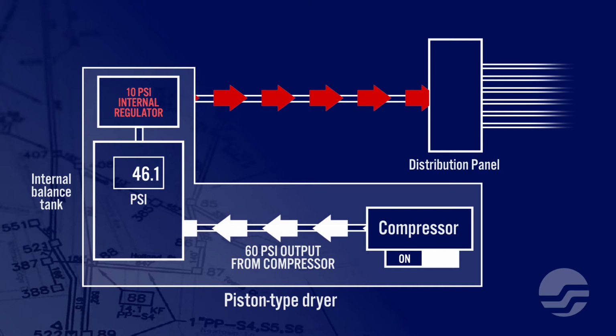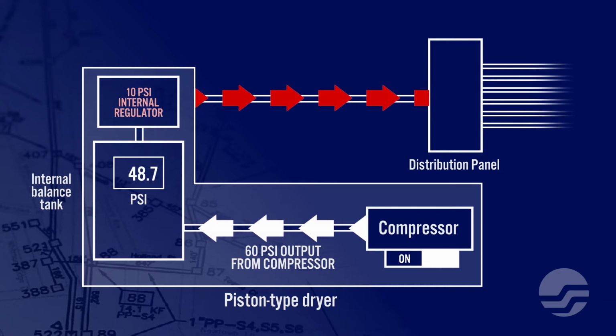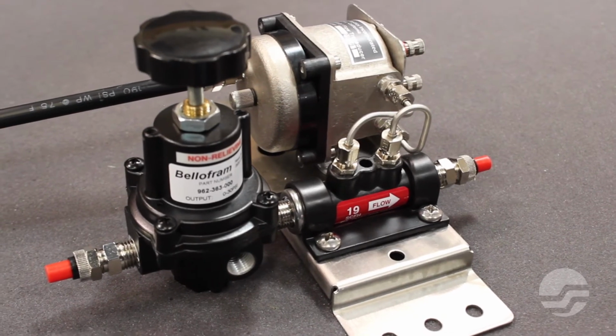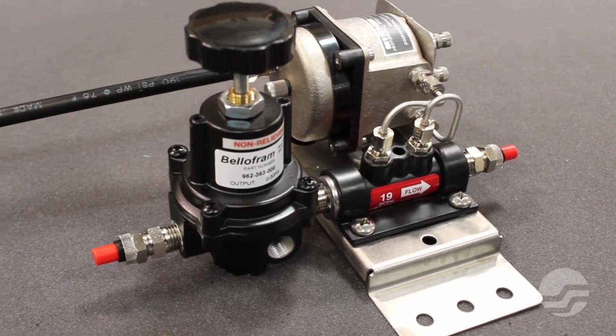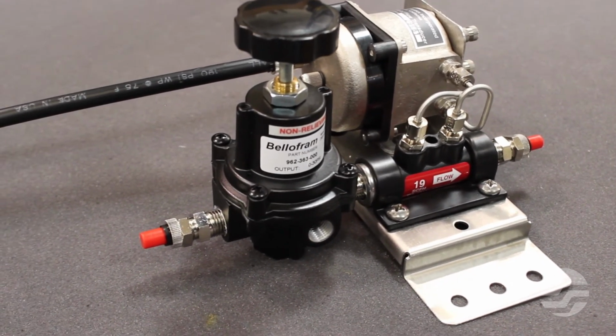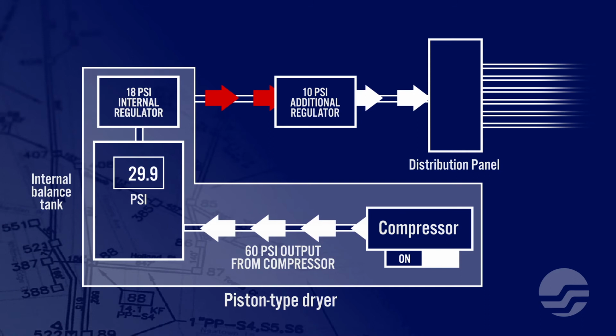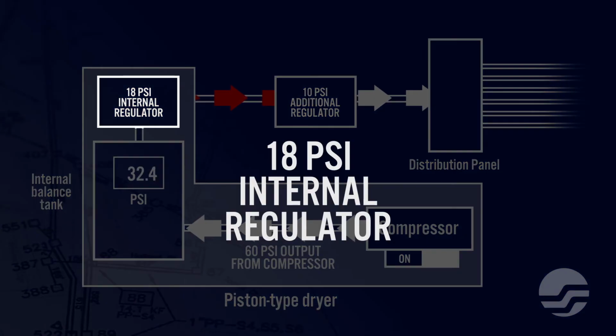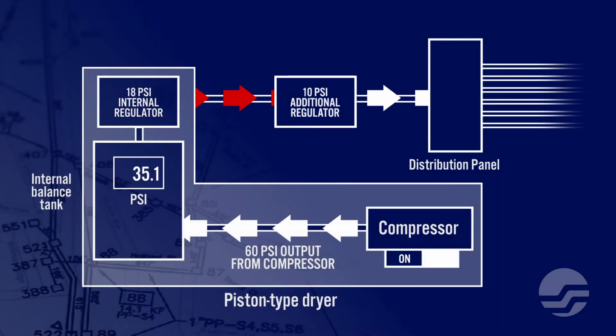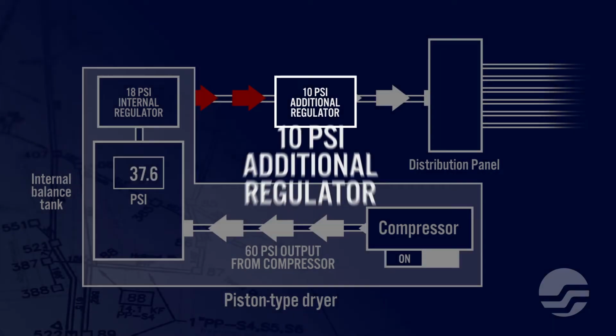To maintain a constant delivery pressure and to eliminate any possible false alarms, install a regulator at the input of the flow measurement assembly. The pressure regulator internal to the dryer unit should be set at 18 psi, while the regulator on the flow measurement assembly should be set to 10 psi.